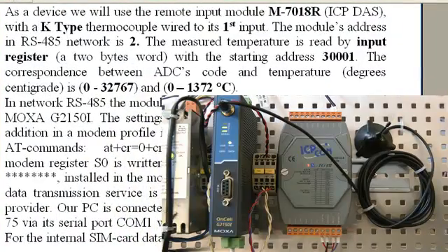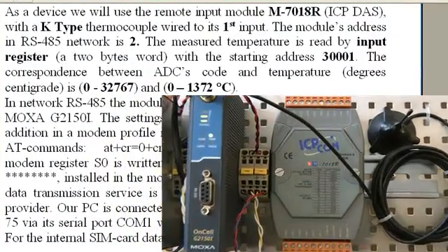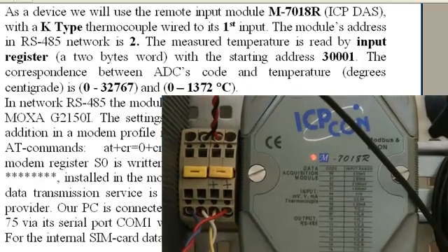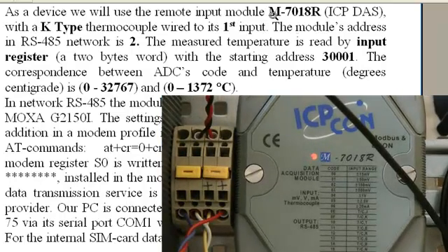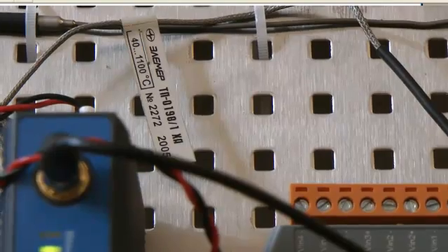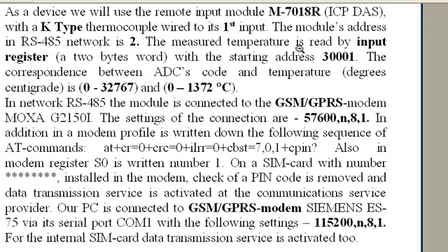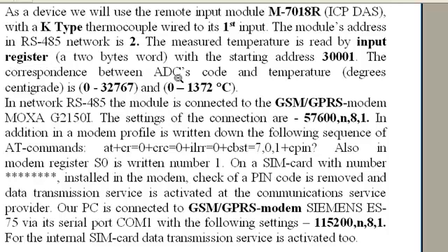As a device we'll use the remote input module M-7018R with a K-type thermocouple wired to its first input. The module's address in network is 2. The measured temperature is read by input register with a starting address 30001.